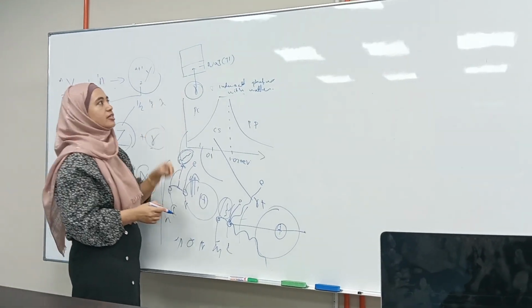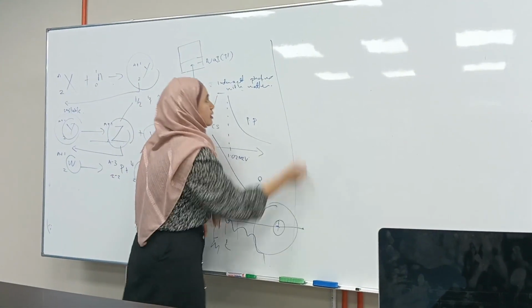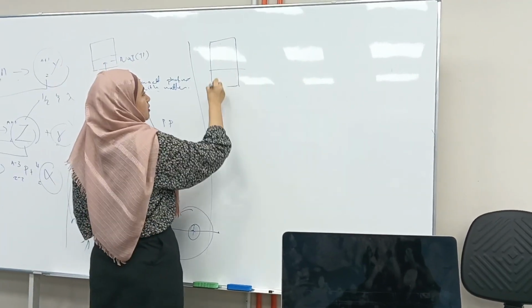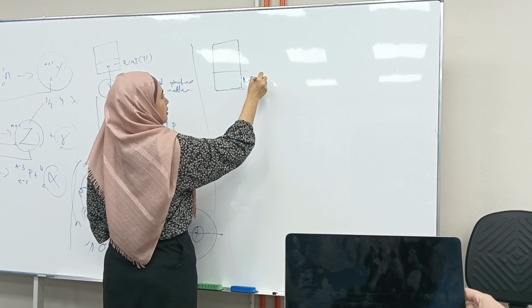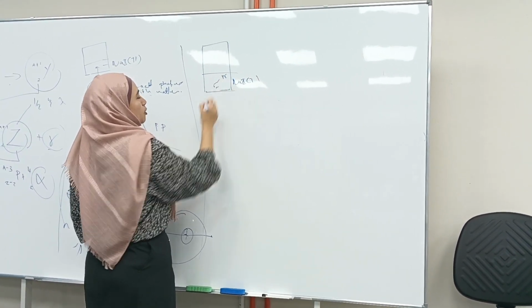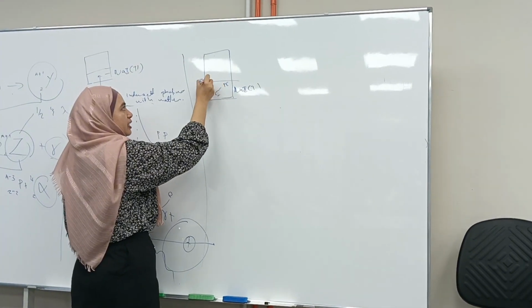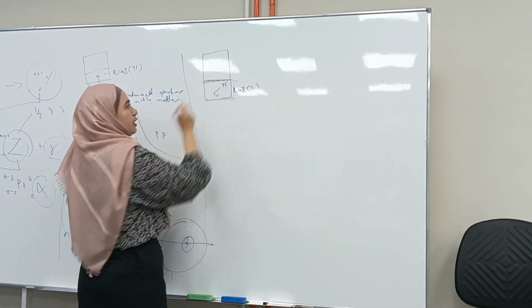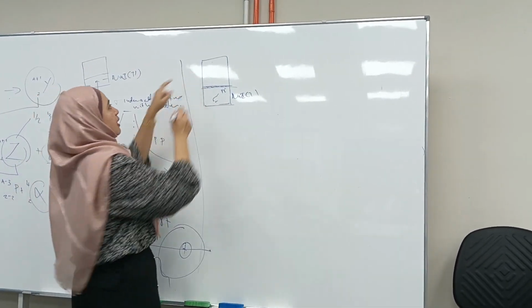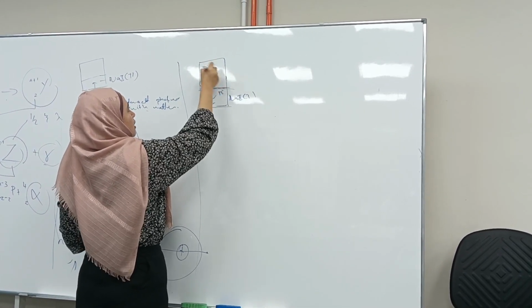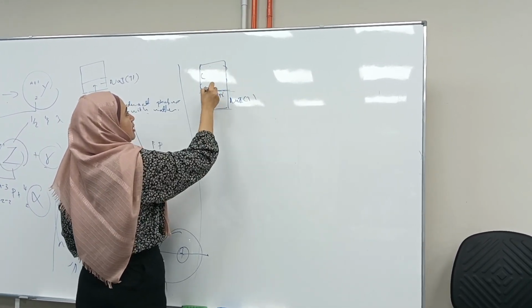So what happened to the scintillation light? The scintillation light at the sodium iodide crystal, the visible light, is either from photoelectric or from Compton. These photons will interact with the photocathode layer of your detector, and at the back there are dynodes.